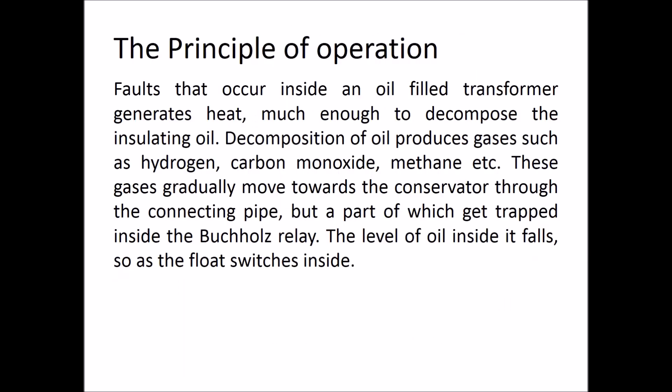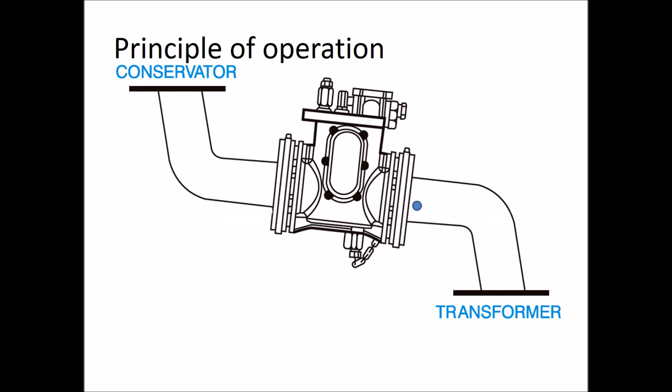The principle of operation: Hydrocarbon oil used in oil-immersed transformers decomposes and forms gases due to heat produced in the event of faults. These gases move towards the conservator and get trapped in the Buchholz relay.